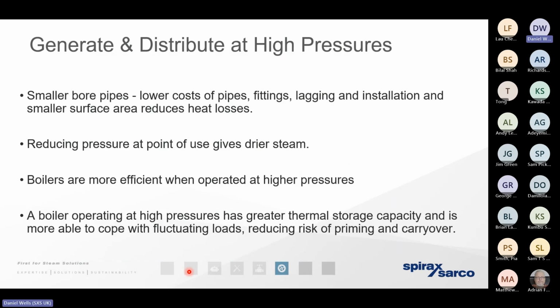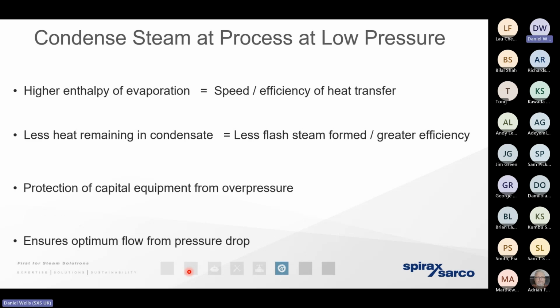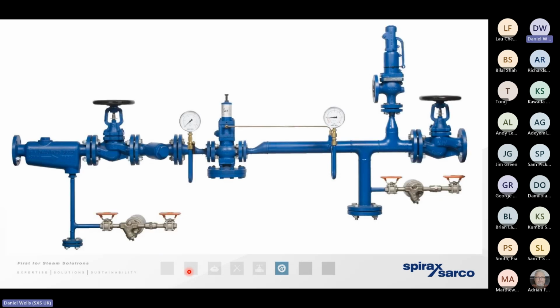So we know the importance of generating steam and distributing steam at a high pressure. High pressure, high temperature, high pressure, high volume, so smaller pipes, high pressure, smaller boiler, and high pressure, a lot of motive energy to move the steam. But we actually want to use the steam at the heat exchanger at the lowest possible pressure. More energy in the steam at a lower pressure. We can control the temperature at a lower pressure. But it also means that we can move the steam from a higher pressure to a lower pressure very, very quickly. So reducing the steam pressure is done across what we call a pressure reducing station.